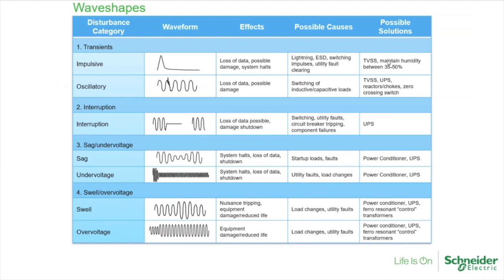Yeah, so a sag and a swell is a short duration, maybe several cycles. But usually if it lasts seconds or longer, then it'll fall under voltage. And an undervoltage lasts not indefinitely, but it lasts for a much longer period of time.